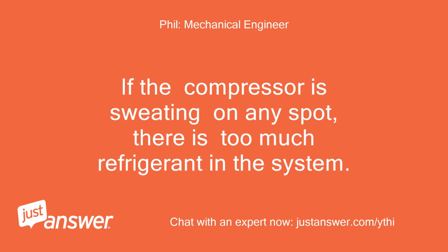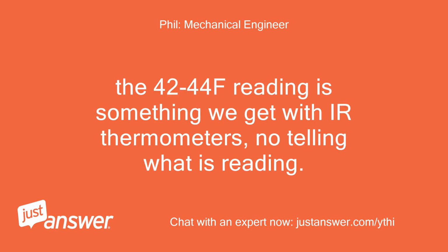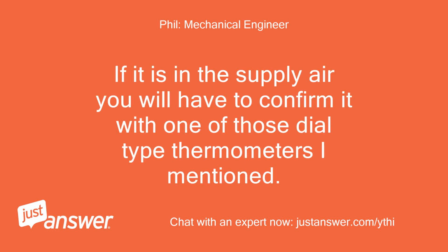If the compressor is sweating on any spot, there is too much refrigerant in the system. The 42-44F reading is something we get with IR thermometers, no telling what it is reading. If it is in the supply air, you will have to confirm it with one of those dial-type thermometers I mentioned.